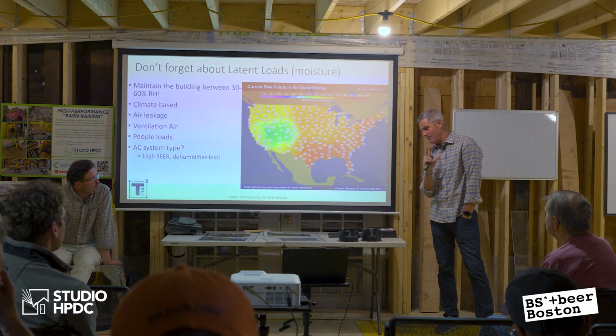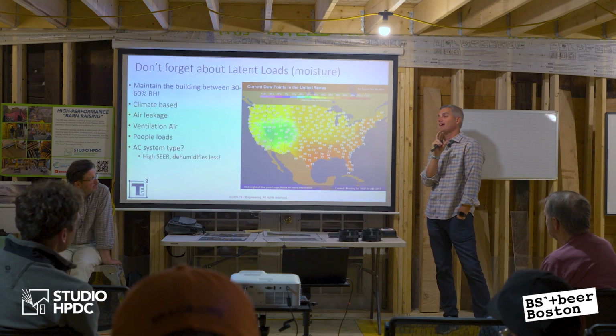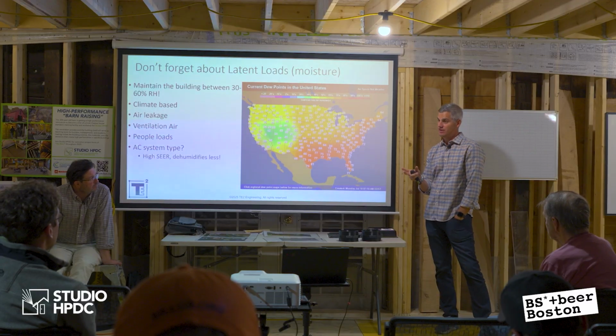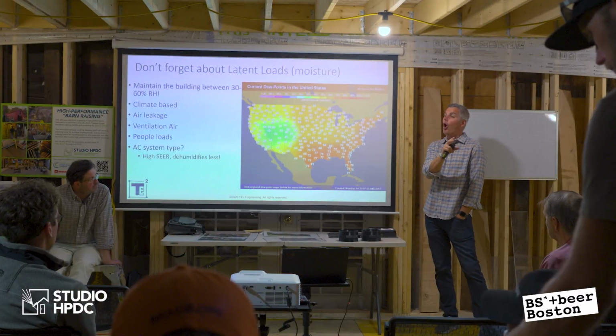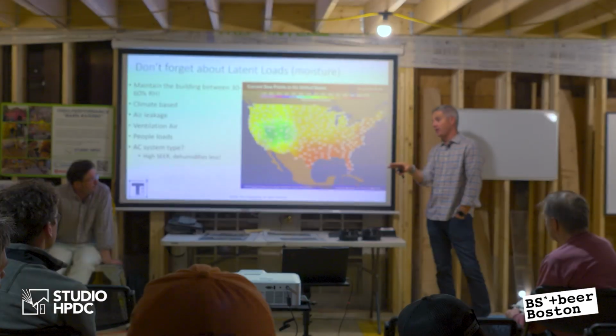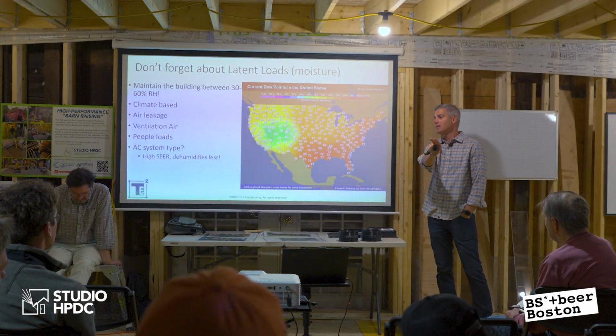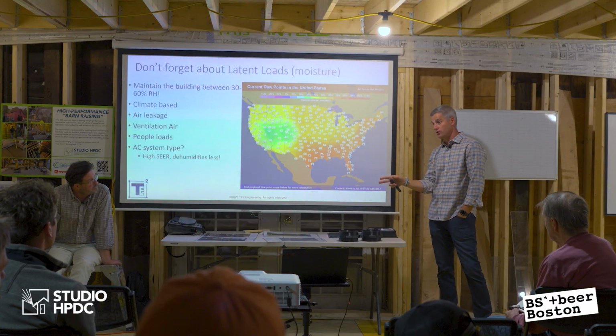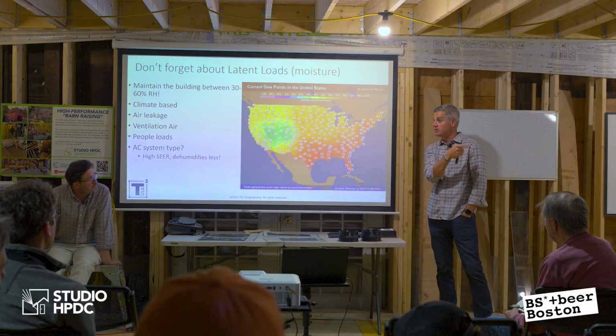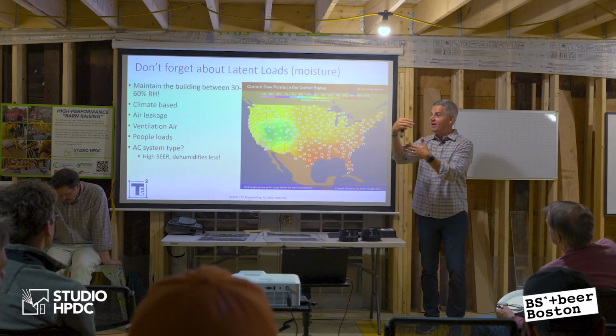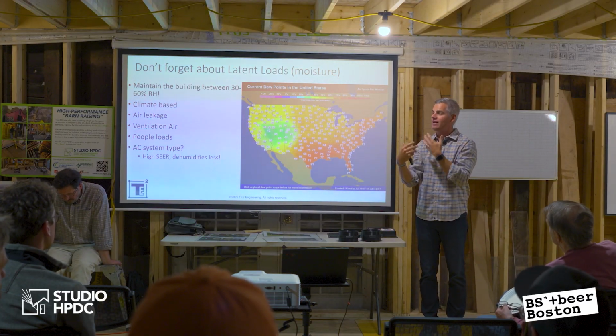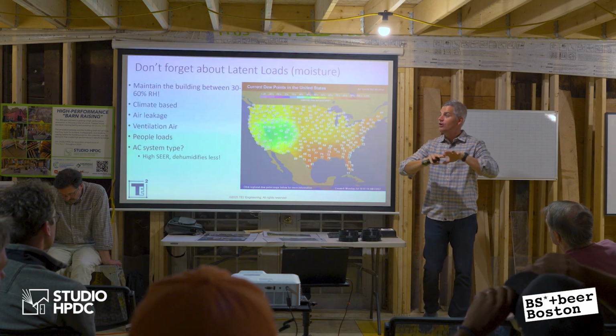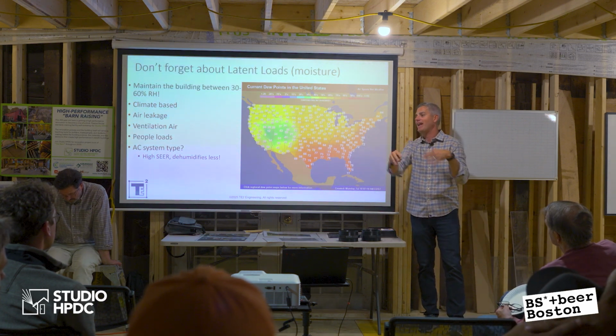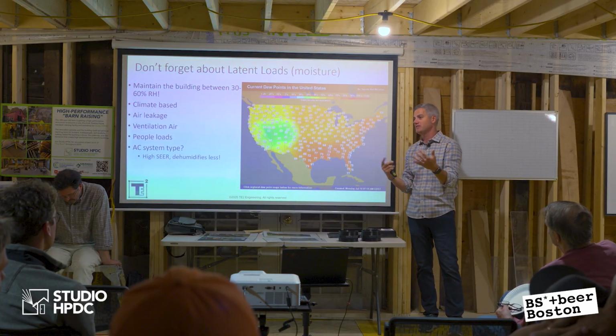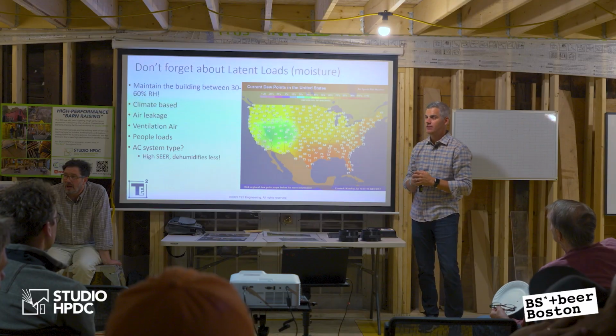So if I have an ERV providing fresh air to the building, and let's say I'm going to go through the air handler ducted system, I would almost always go to the return side of my air handler rather than the supply side. There are times we've gone to the supply side, but in most cases the return side. The reason is I get the post-treatment we talked about before. I have a filter on that air handler, a heating and cooling coil, and a blower motor. I can then redistribute all of that fresh air to all spaces downstream, and I get the ability to post-filter it, post-heat it, or post-cool it, depending on the season. It's not just raw ERV air.